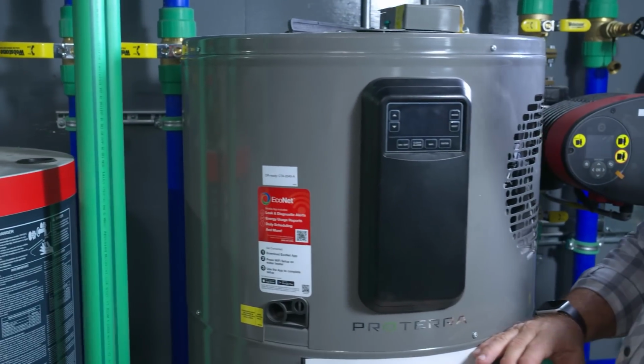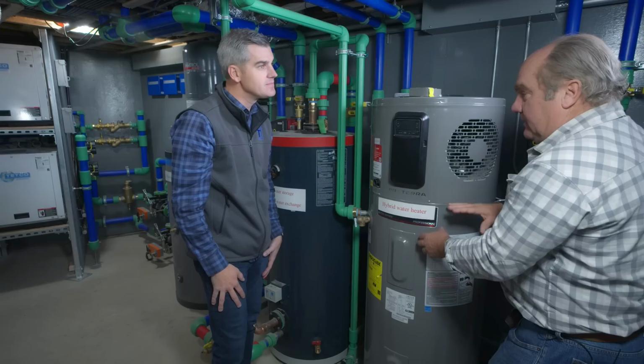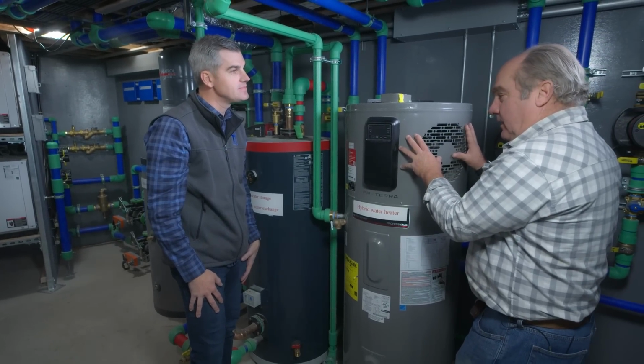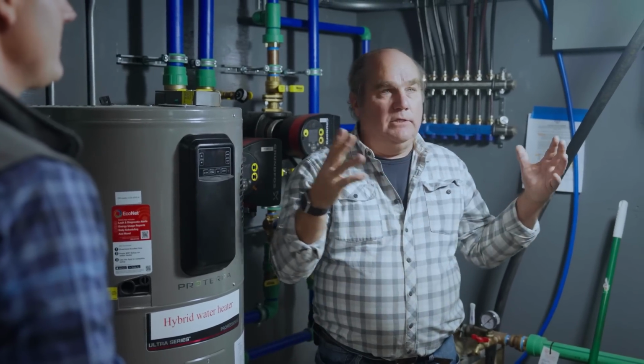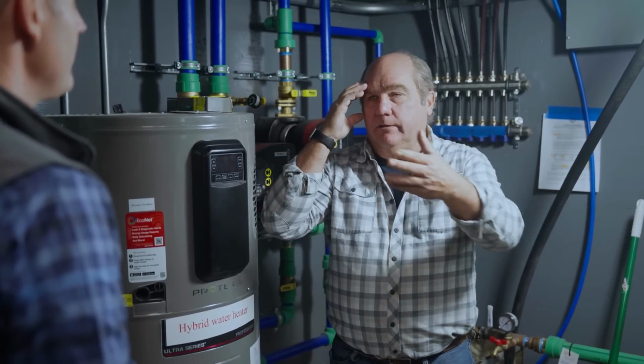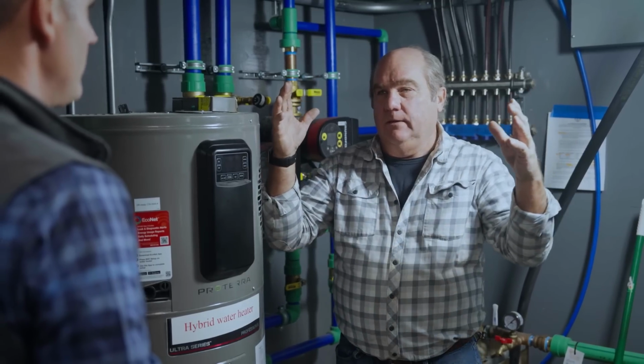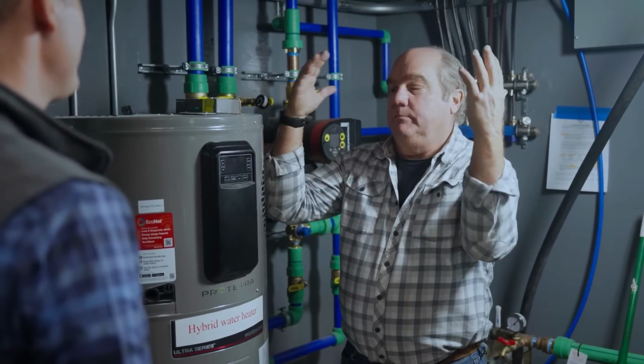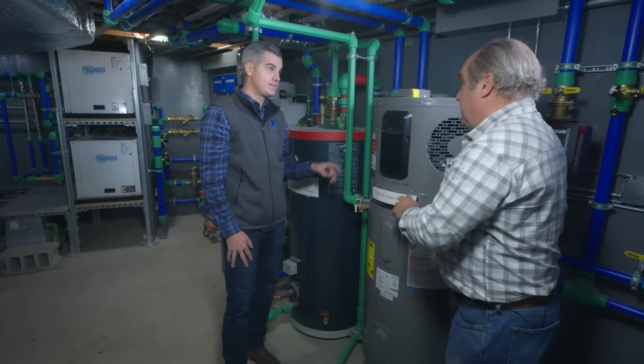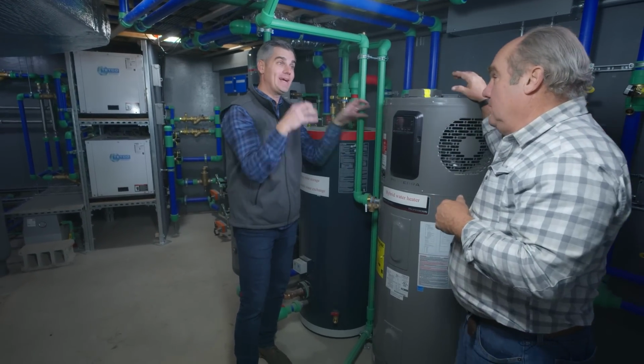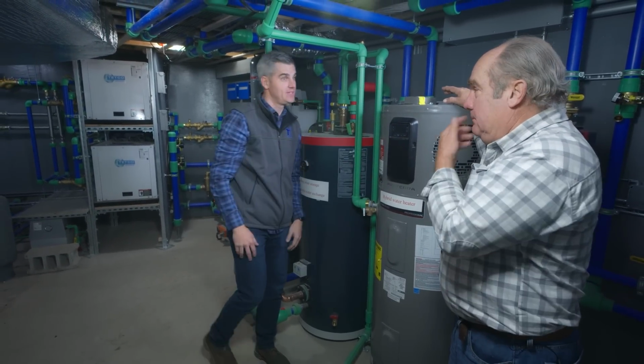This is a hybrid water heater, and it has a little element in it. But what's most important is it's got a heat pump on top. What that does is these rooms can be 90 degrees because you've got all the heat coming off the pumps and the piping. So instead of having it be too hot, you have it go right into the hot water, so you have plenty of hot water. This is going to air condition this room and take that heat and put it into the hot water. It's pretty smart, amazingly efficient.